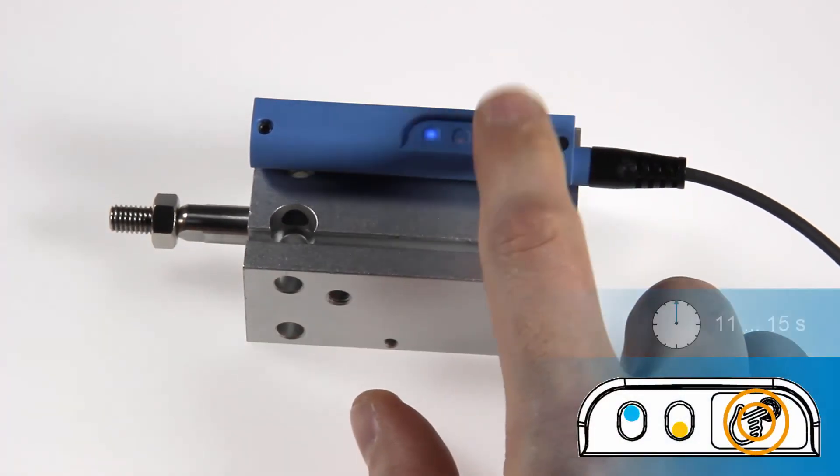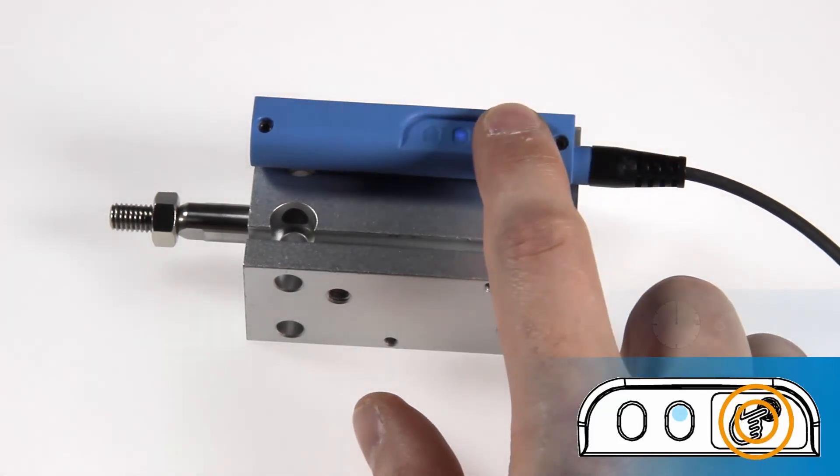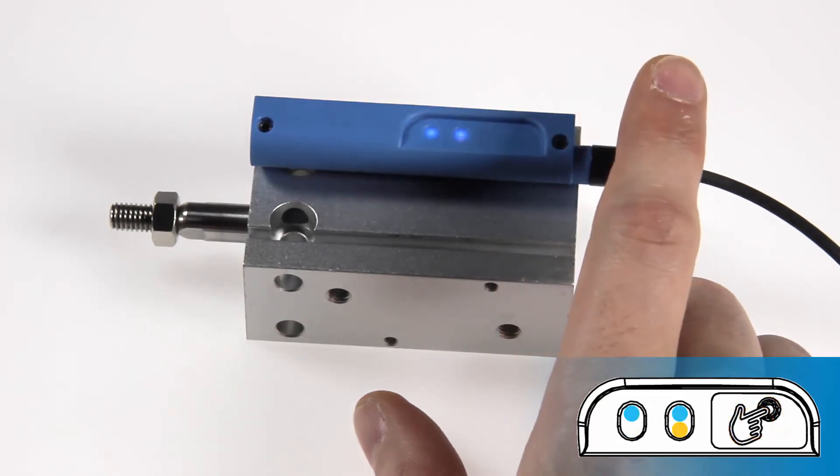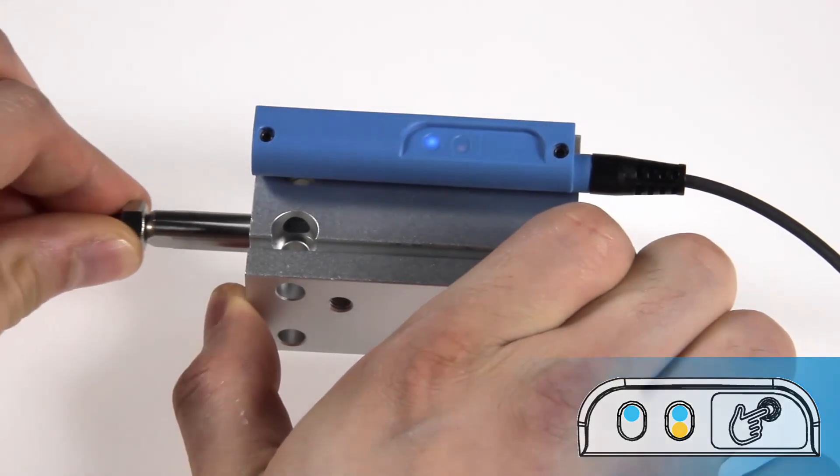Press the keypad and then hold the keypad between 11 and 15 seconds. The blue status LED flashes slowly. Lift your finger and then hold the keypad between 3 and 6 seconds. The yellow operating LED and the blue status LED flash slowly. The switching point is set as soon as you lift your finger.